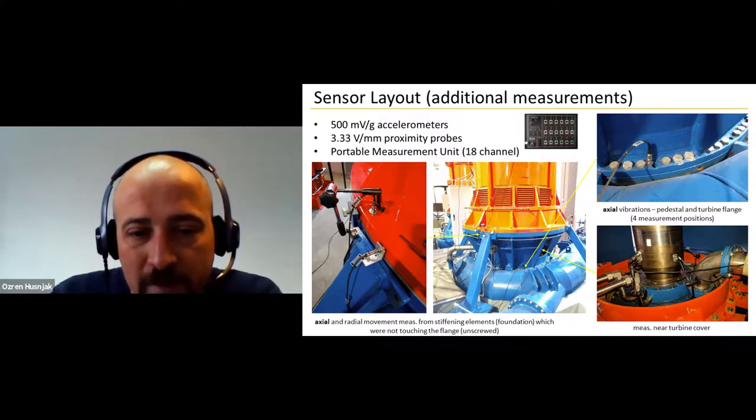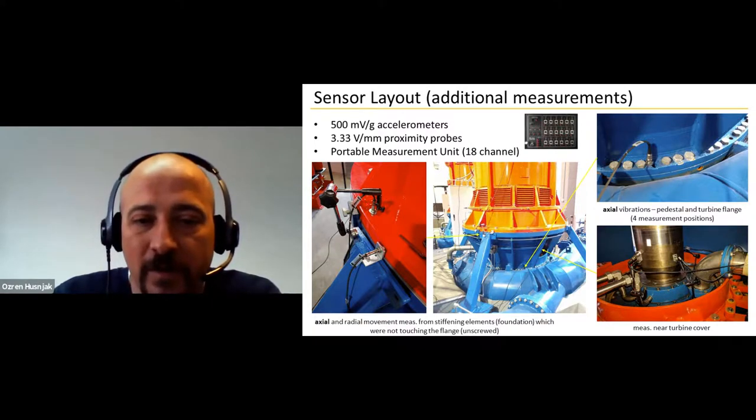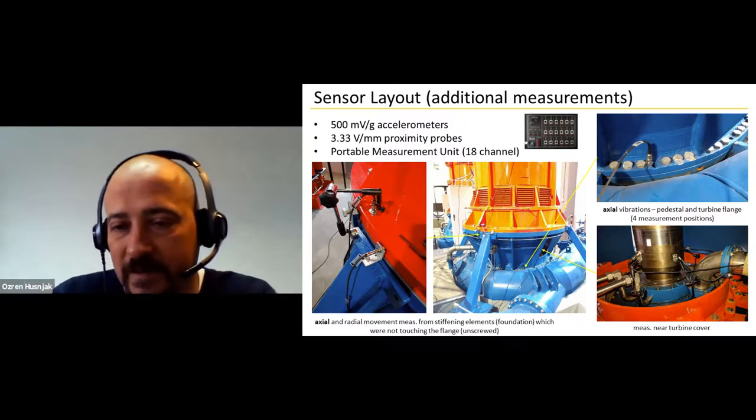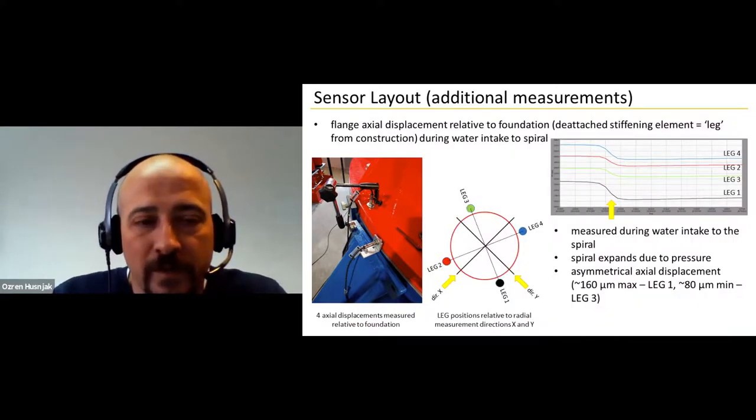And we also put four accelerometers below, on the connection between the pedestal and the spiral. So in this area here. And these four sensors in the axial, measuring the displacement, and four sensors in the axial measuring accelerations, turned out to be very valuable. So instead of looking at the radial direction, we focused more on the axial one. There is a zoomed-in picture of the sensor, and these are just some additional measurements in the turbine cover.